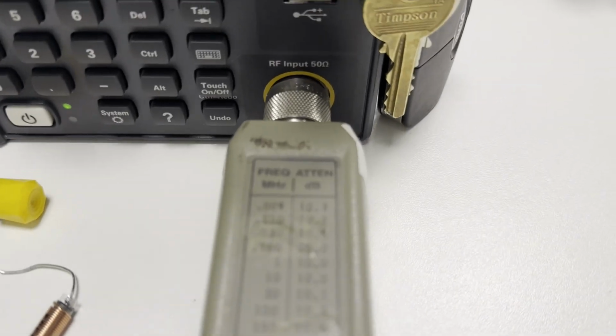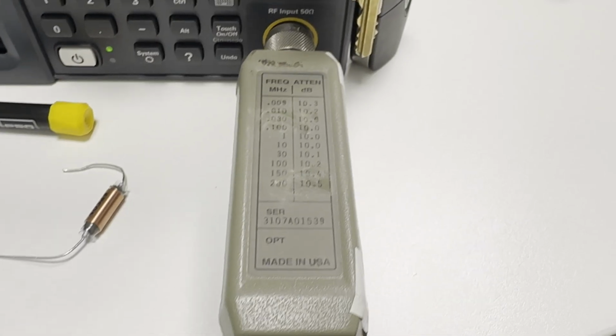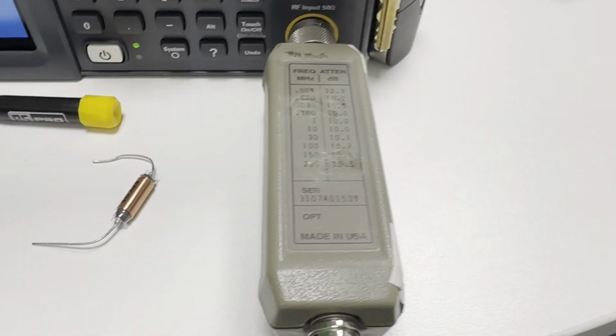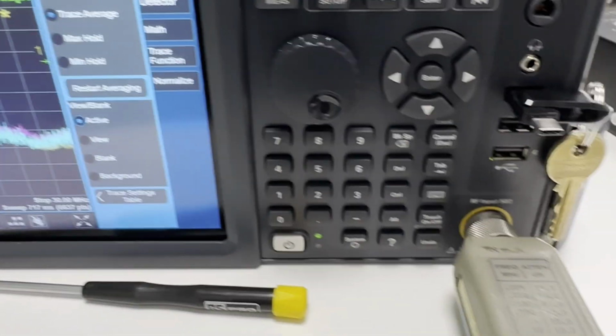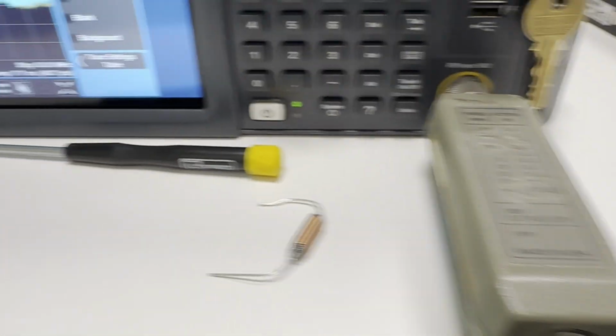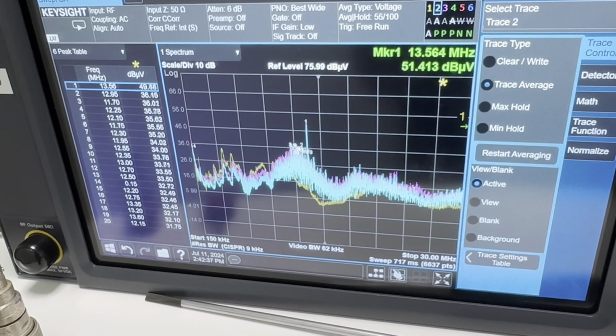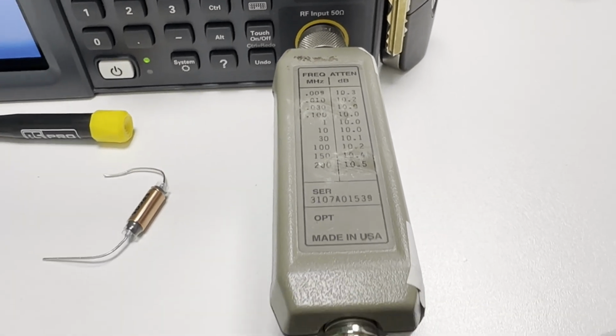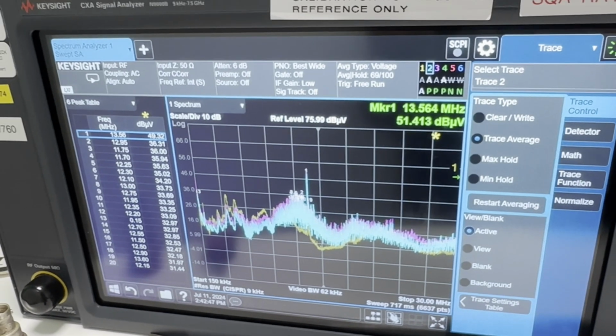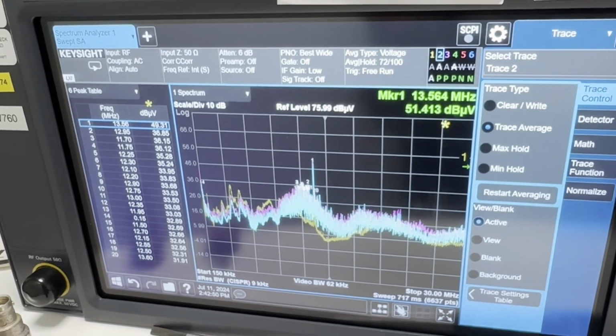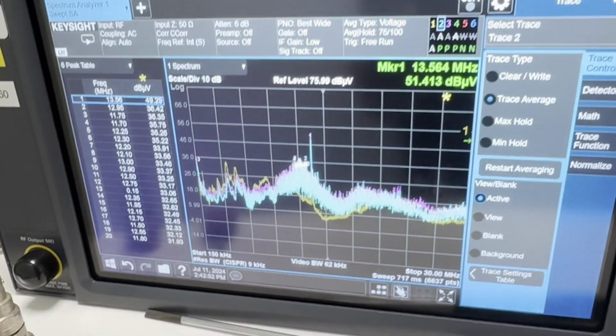The other thing we can do, we can also add an attenuator to the signal path, to the LISN output, and basically that was the issue with the overload, and you can see the error is gone now. So adding this attenuator helps to remove potential issues, and overdriving the Spectrum Analyser, which can be a problem, so it can destroy the Spectrum Analyser. It still comes up occasionally.